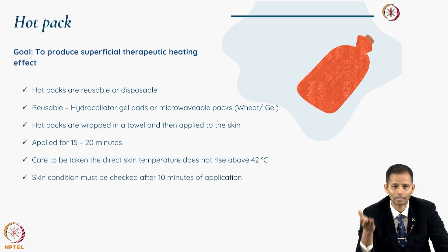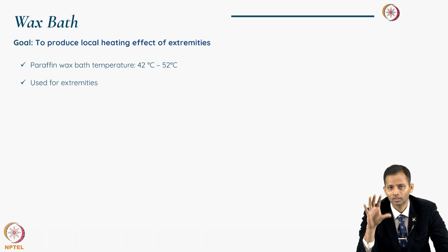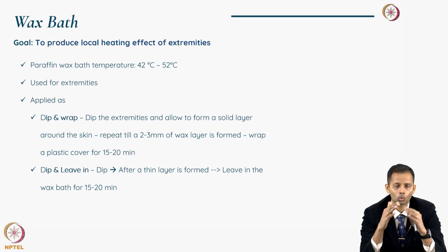It's more of a local heating effect on the extremities, because for extremities it's useful to use wax. The wax used is paraffin wax. The temperature maintained is 42 to 52 degrees Celsius. Though we say 52 degrees Celsius, it is just to keep the wax in liquid form. When you use it as a modality, there are two different ways of application. One is dip and wrap, where you dip the extremity into the wax bath and then allow it to solidify. Even though it appears that the temperature is high, as soon as it is applied the wax solidifies by releasing heat, so the temperature actually transferred to the skin will be much lower. That is why it is within the tolerable range.